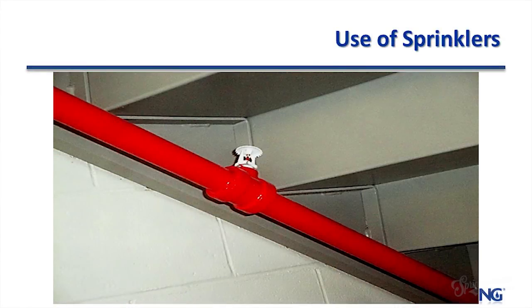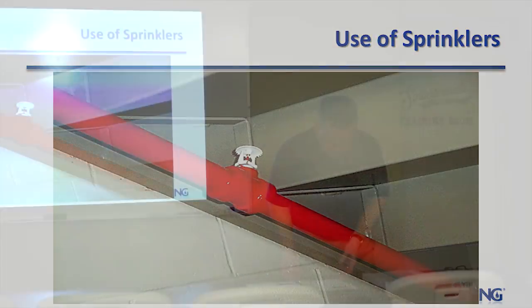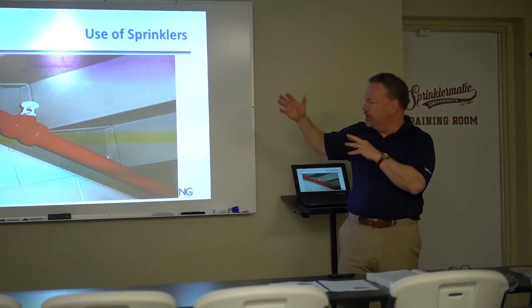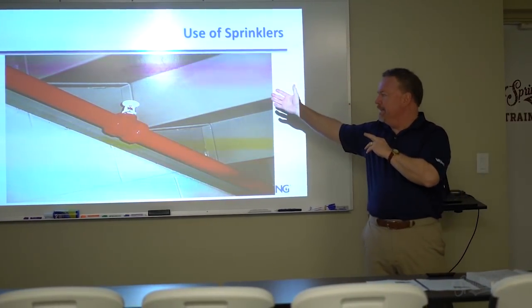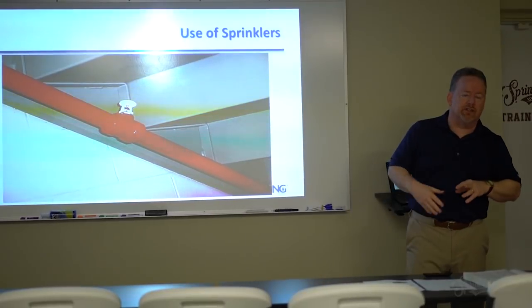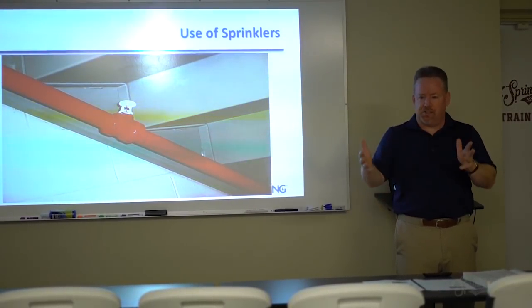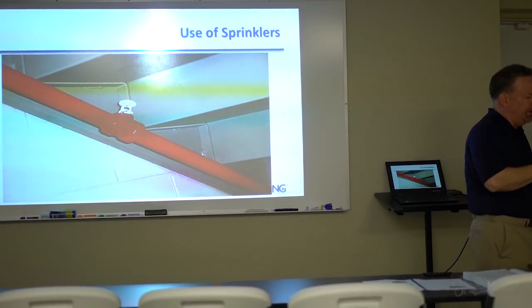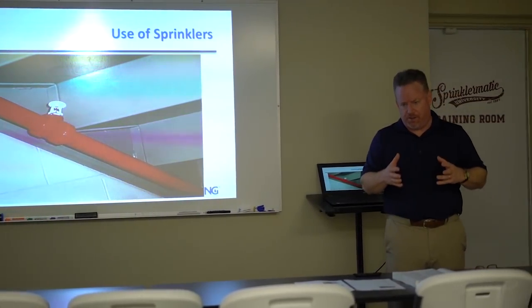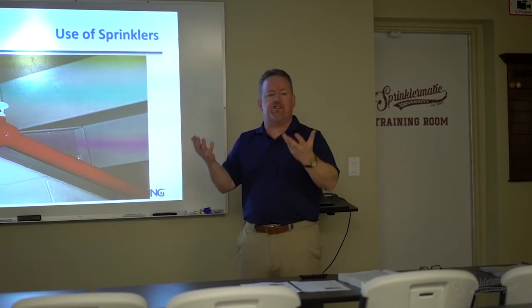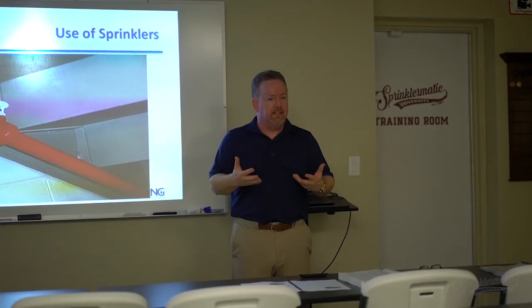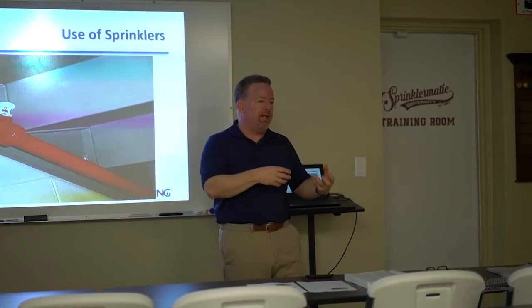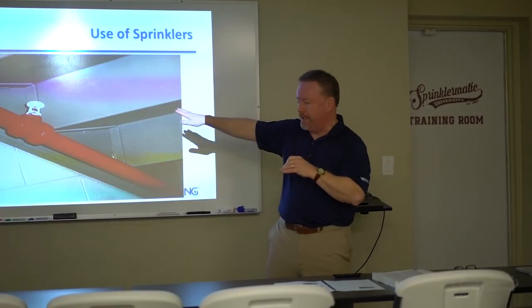Let's look first at the use of sprinklers. When we look at a sprinkler — its deflector, frame arms, and orientation — NFPA 13 has very specific guidance on how that sprinkler is to be used. The design criteria matters because the sprinkler will deliver a certain amount of water, and that amount depends on the size of the orifice and the pressure of the water flowing through it.